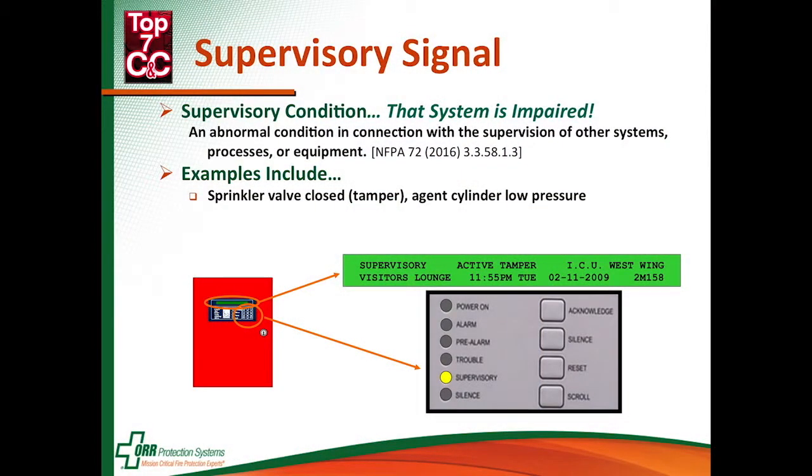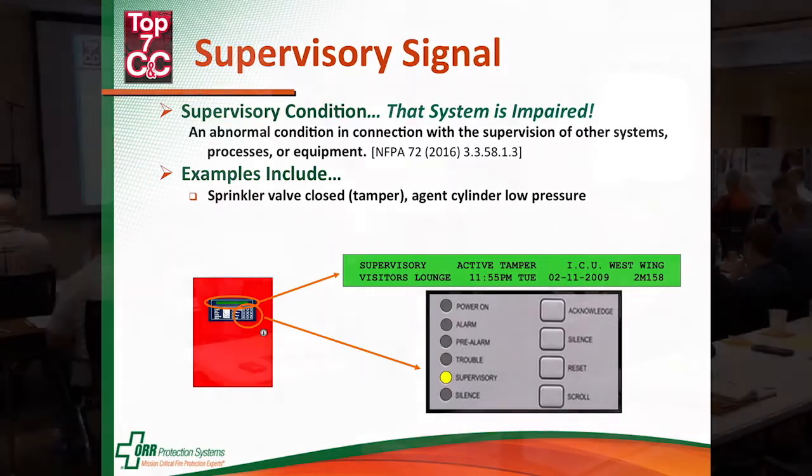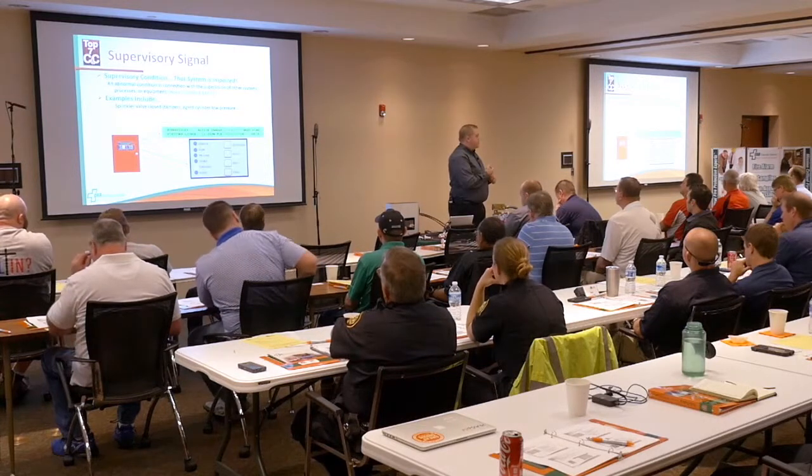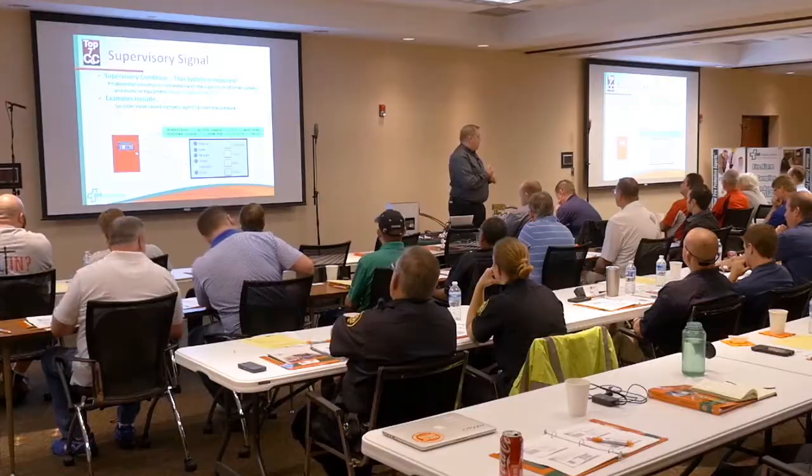Supervisory conditions — we use fire alarm systems to monitor other systems in the building. The best example is a sprinkler system. We supervise the sprinkler system via tamper switches or monitor switches on valves to make sure those sprinkler valves are in the correct position. When we talk about suppression systems, we look at pressure switches to make sure the tank pressure is correct. I've even seen a hospital example where they used the fire alarm system to monitor the temperature in a blood cooler — if it got too hot, it brought in a supervisory signal at the panel, used as a monitoring device, which is allowed by the code.